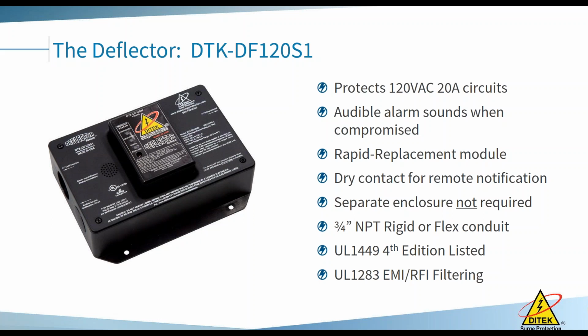It also, if you'll notice from that picture in the bottom left, you'll see one of the caps over a knockout that have dry contacts, normally open, normally closed dry contacts. So if this device were ever tampered with, lost power and or self-sacrifice, it's going to report to you via that monitoring module or whatever you have it hooked up to for a trouble code. And this is a lot easier to sell to our customers because now, with the dry contacts, you can actually program into the panel, depending on the manufacturer, it could be 10, 20, or 40 alphanumeric characters to say, hey, AC protector blown. So anybody walking by that panel knows exactly why it's in trouble, and they're going to call you.